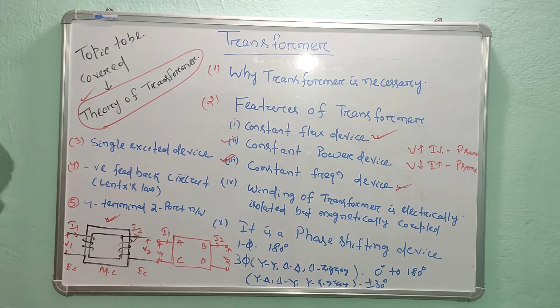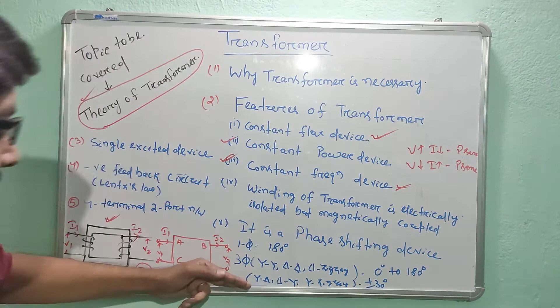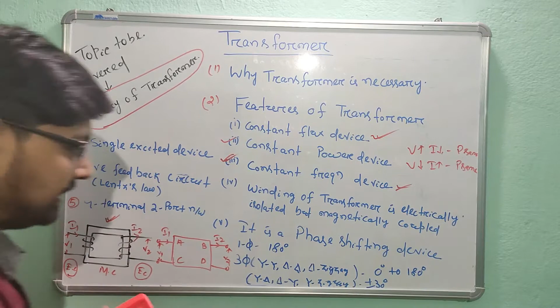Next is, it is a phase shifting device. For single phase, it is a 180-degree phase shift, but for three phase there are different types of three phase transformers - star star, delta delta, star delta, zigzag. The phase shift is 0 degree to 180 degree, but for star delta or delta star the phase shift is plus minus 30 degree, that is 180 degree plus minus 30 degree. So transformer is a phase shifting device.